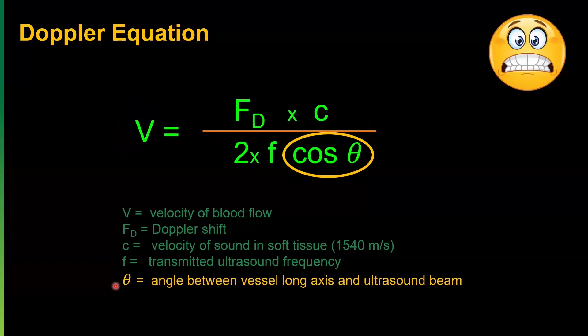So it would look like this. Here's the transducer sending that Doppler sound beam down this way. It intersects the vessel here. So what is this angle between the vessel wall and the Doppler sound beam? And why do we care? Well, here's the error in the cosine part of this, meaning this is the angle, so the cosine of that angle. But again, you don't have to figure that out. Your machine will. But here's the error. And you can see once we get to about 60 degrees and beyond, that error gets unacceptably large. At this point, if you're trying to measure velocities and you've got an angle of incidence that's say over 80 degrees, you may as well go to the velocity dartboard and just start throwing darts at the wall to see what the velocity is, because it will not be accurate.